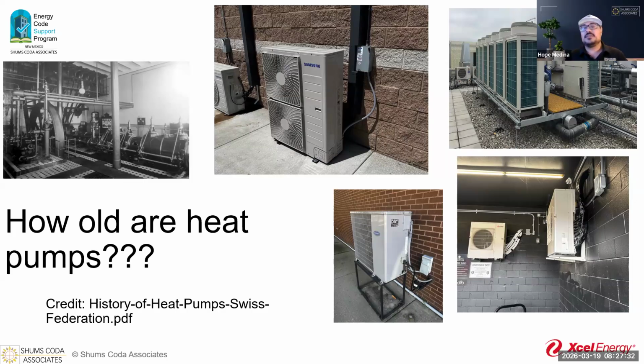Now, heat pumps, because you get a variety of different applications, right? You get standard air source heat pumps, you get mini splits, you get a lot of different options. Often what I see is a lot more use of piecemealing the different components together to get a pretty precise calculation on the load they want to end up with. Because they can get down to 8,000, 7,000 BTUs of additional load, fairly precise depending on how many they want to put in a system, how many rooms they want to specifically have, maybe their own mini split system, or things like that.